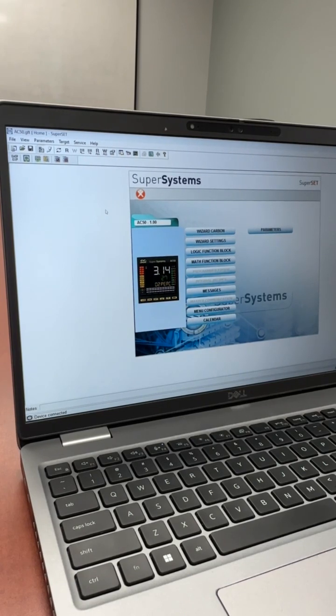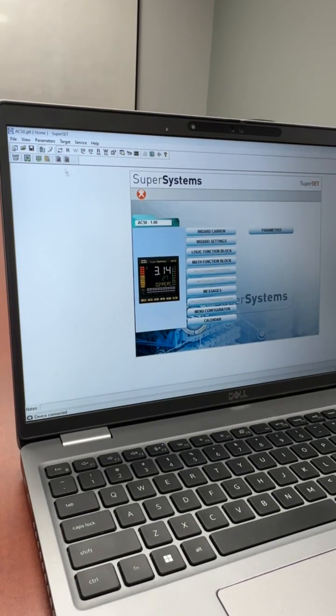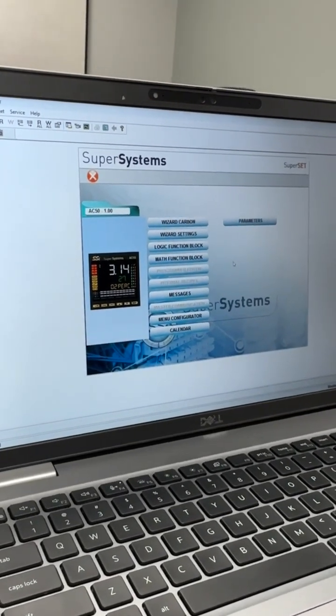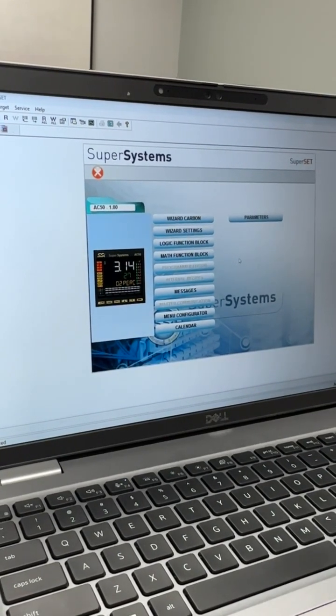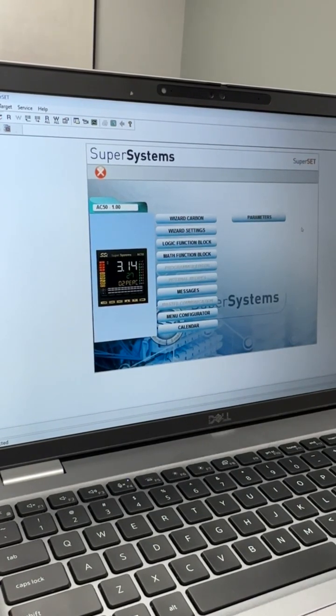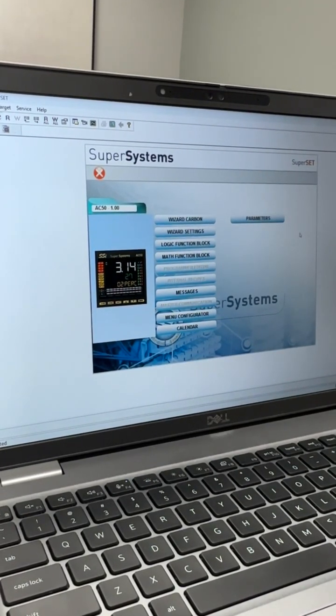Once the values have been pulled in, we will want to select online mode. By selecting this, this will keep the Superset software and the AC50 settings current between the two. So if any changes were made within Superset software, they would be written down to the AC50, as well as any changes in the AC50 would be uploaded to the Superset software during communications.